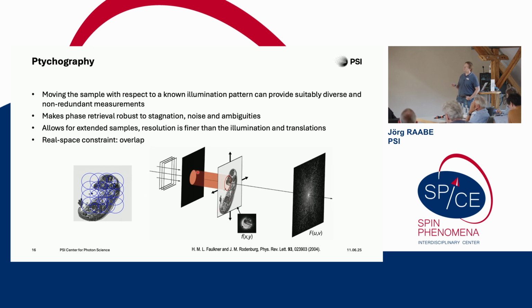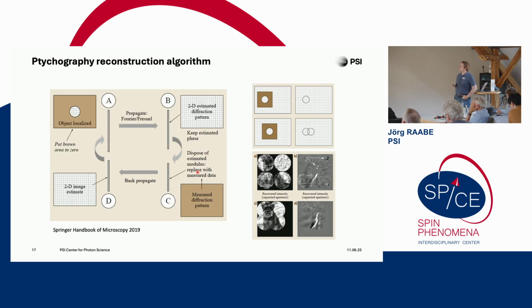So the first attempts were really with a parallel beam, but now we typically use a zone plate to focus the beam. The beam on the sample is typically a few hundred nanometers or microns in size, and then we record the diffraction patterns in different, overlapping areas of the sample, and then we send this into a reconstruction code, an iterative code. The constraints from these overlapping points in the end enable a very robust reconstruction algorithm, to reliably retrieve the sample information.